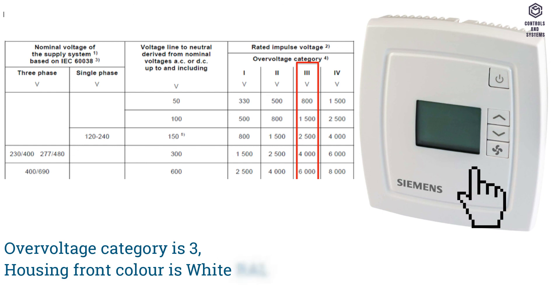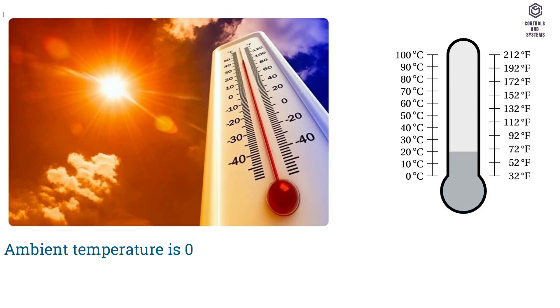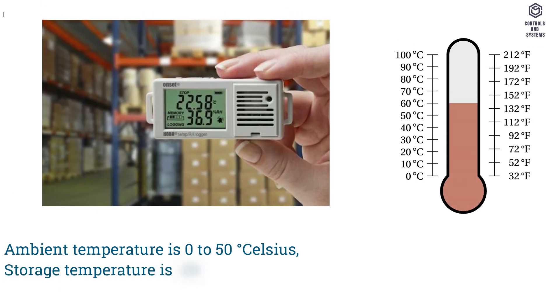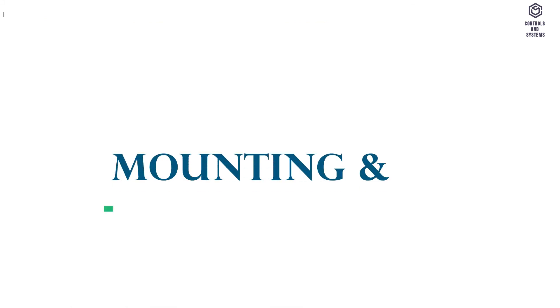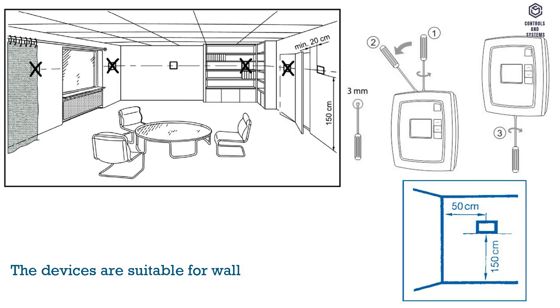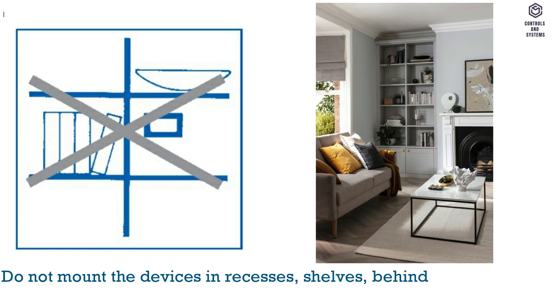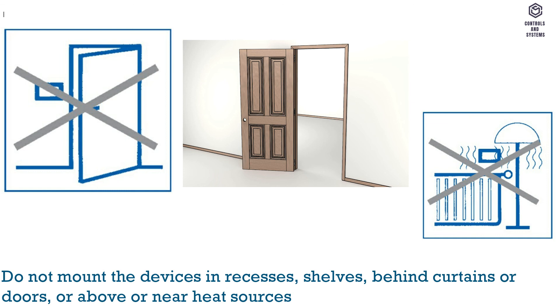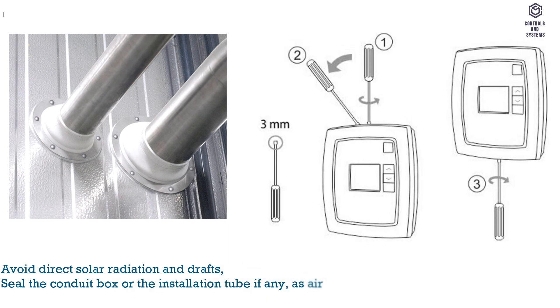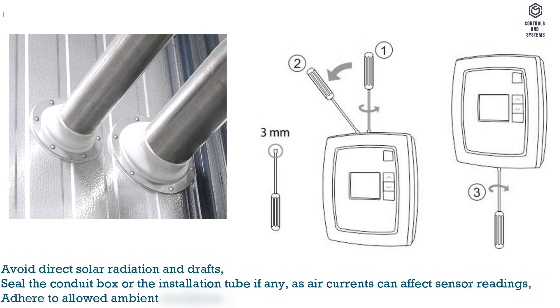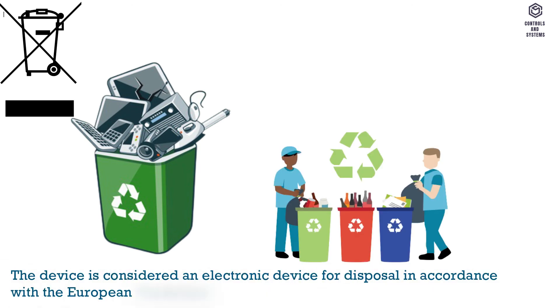Housing front color is white (RAL 9010). Weight without packaging: 0.18 kg. Ambient temperature: 0–50°C. Storage temperature: −20 to +78°C. Ambient humidity: maximum 90% RH. Mounting and installation: devices are suitable for wall mounting; recommended height is 1.5 m above the floor. Do not mount in recesses, shelves, behind curtains or doors, or above or near heat sources. Avoid direct solar radiation and drafts. Seal the conduit box or installation tube, as air currents can affect sensor readings. Adhere to allowable ambient conditions.